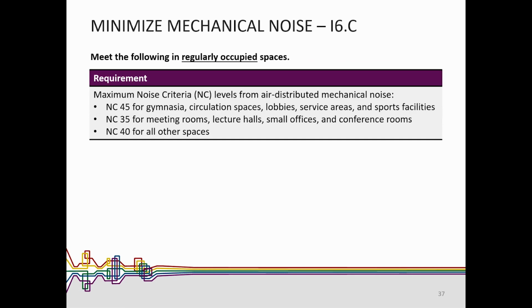Next is minimizing mechanical noise through the noise criteria. There are different thresholds for different types of spaces, with the strictest being for meeting rooms, lecture halls, offices smaller than 300 square feet, and conference rooms, where speech communication without loud background noise is most important. The equipment and the air distribution system are really critical here. The requirement is NC levels from air-distributed mechanical noise, so it doesn't take into account some of the other non-mechanical noise sources mentioned earlier.